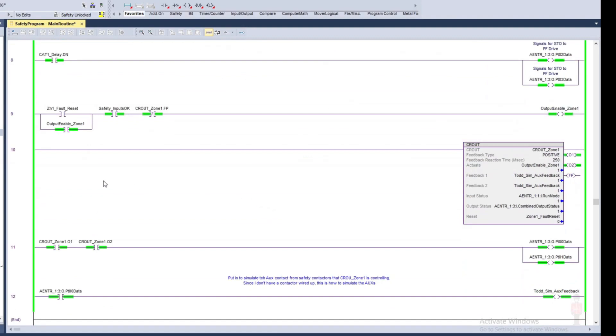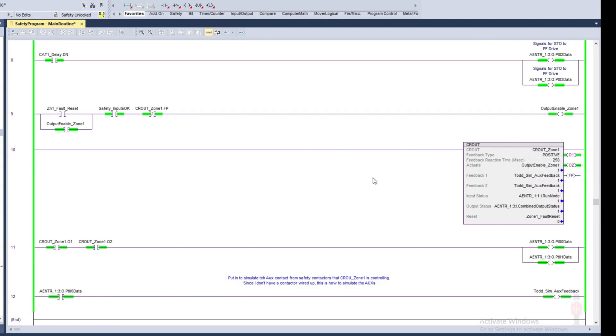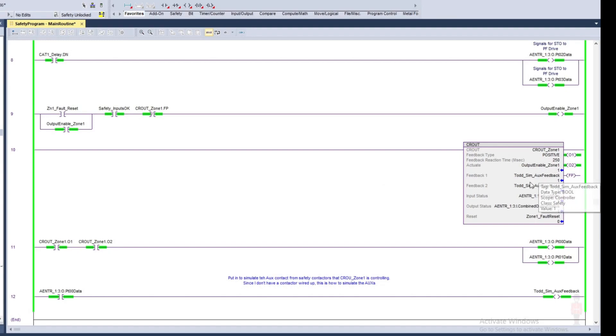The other instruction that I'm using is a configurable redundant output. This is going to be going to my safety contactors, and in my case here I'm just using a simulated feedback. Normally I would just have the feedbacks from my safety contactors, they maybe would be in series and I would have them go to another safety input.